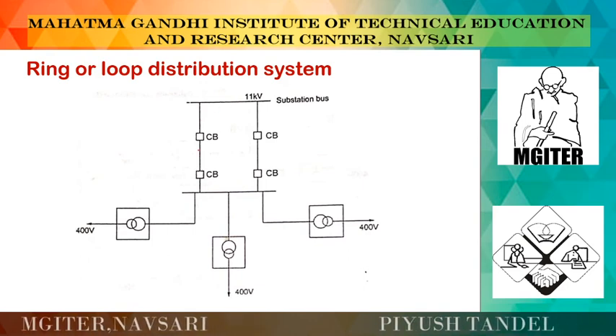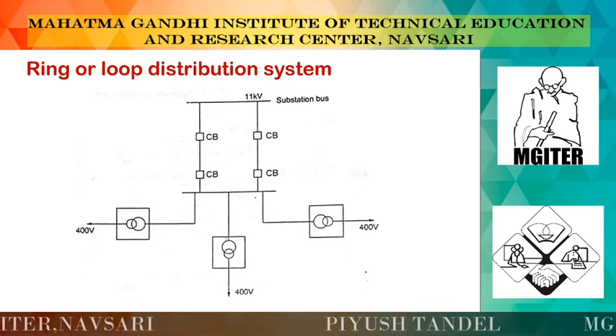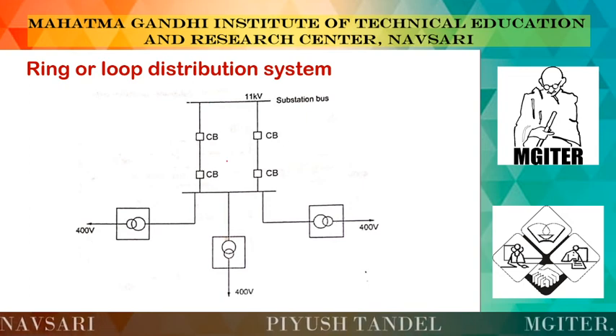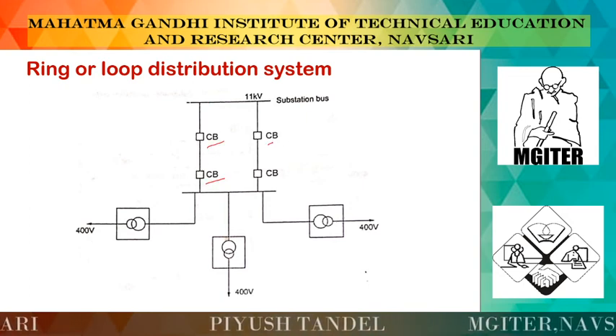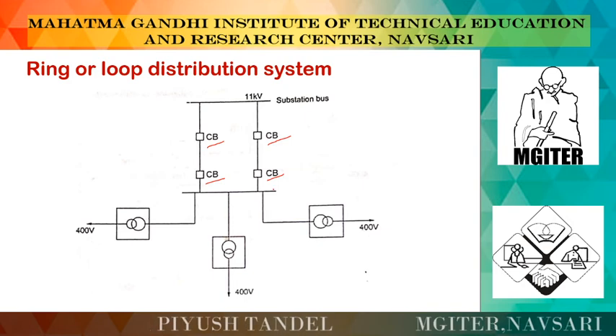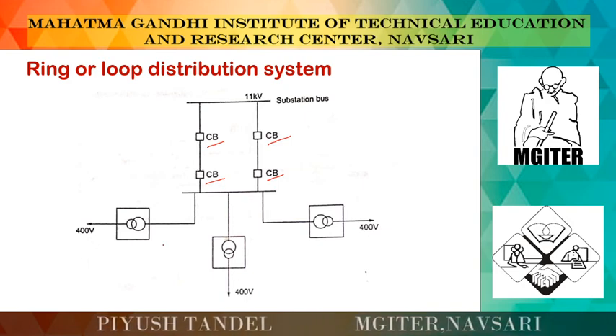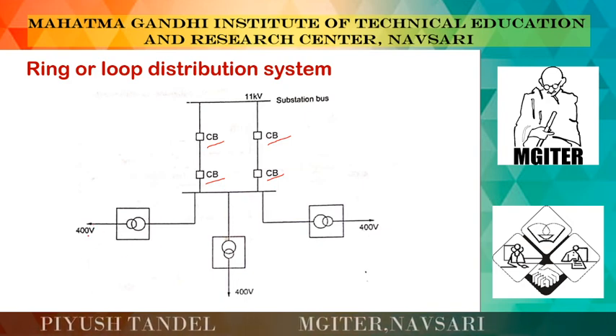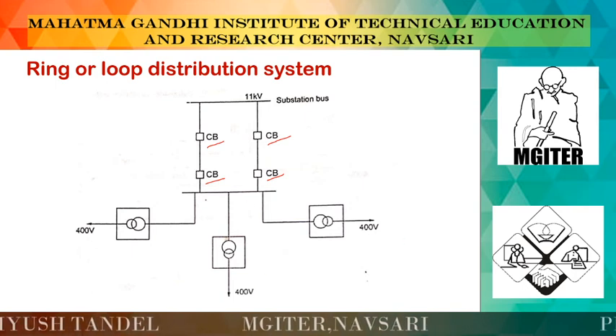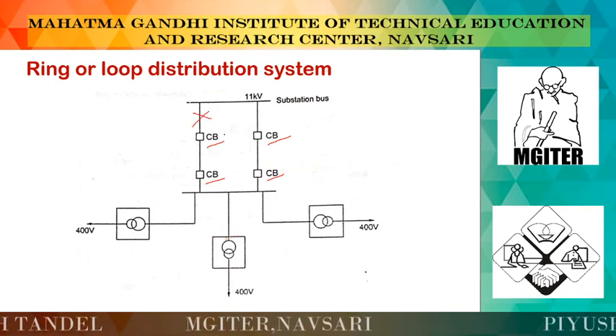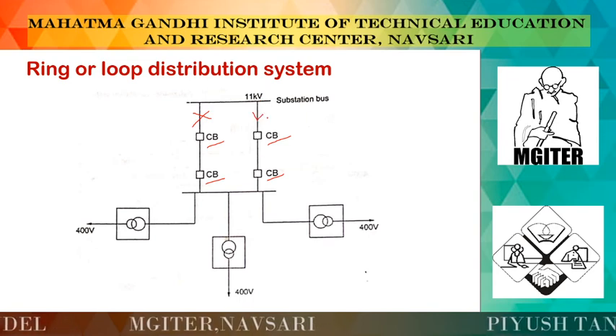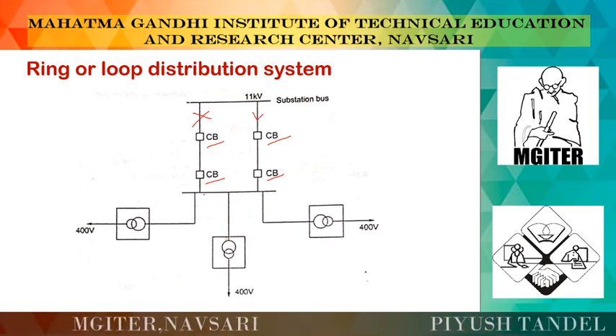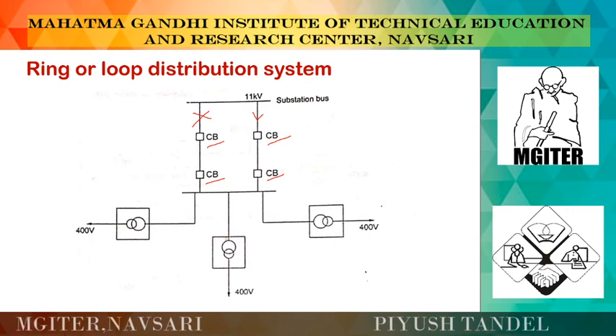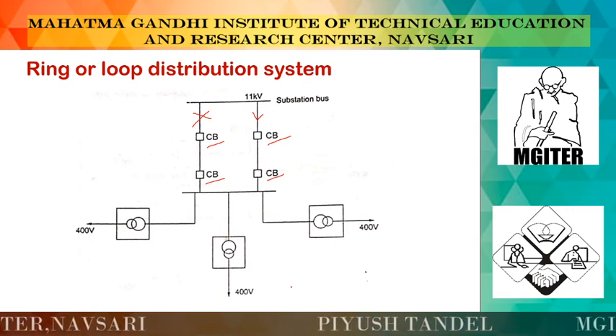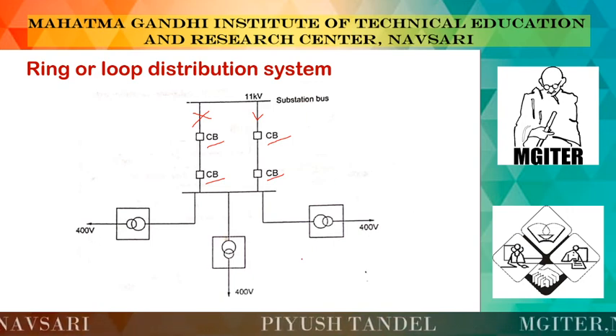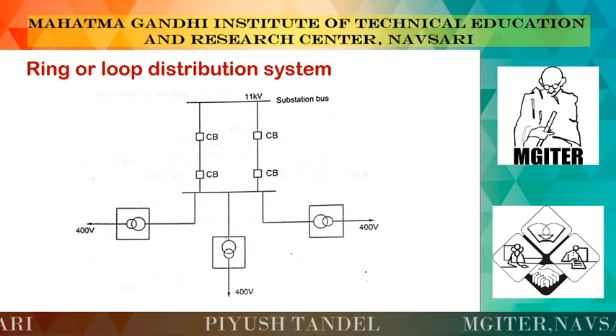Now the second one is the ring main or loop distribution system, where we have a loop or ring type arrangement. That is why we call it a ring main distribution system. Here we have a circuit breaker over here and two circuit breakers over here, and this is the other main bus from where we get our power, converting 11 kV to 400 V at the consumer side. Now if a fault occurs on this bus, this bus goes inactive, and all the power flows from the other side, feeding all the loads. So the continuity of power supply is maintained inside the ring main or loop distribution system.